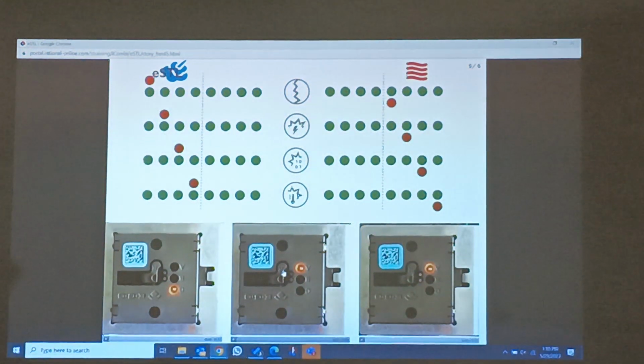High temperature, okay, short circuit. As I told you, the first four is for the steam and the second four is for the hot air. So as you can see, count here: 1, 2, 3, 4, 5, 6, 7, 8. The first one is disconnect, the second one is the sensor short circuit, the third one is the sensor out of logic area, the fourth one is high temperature.